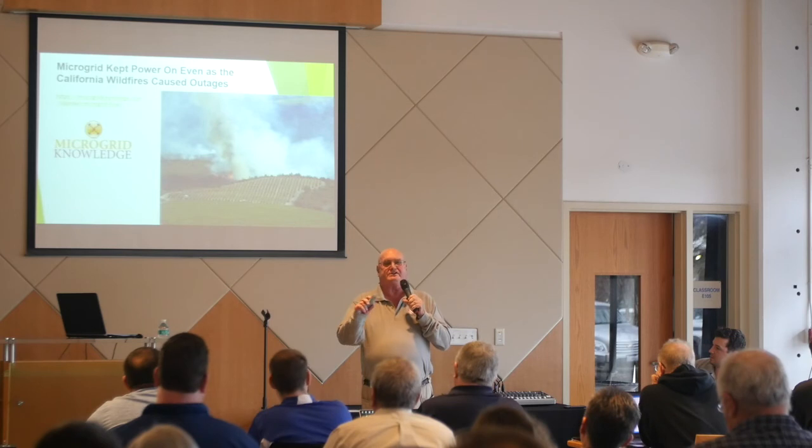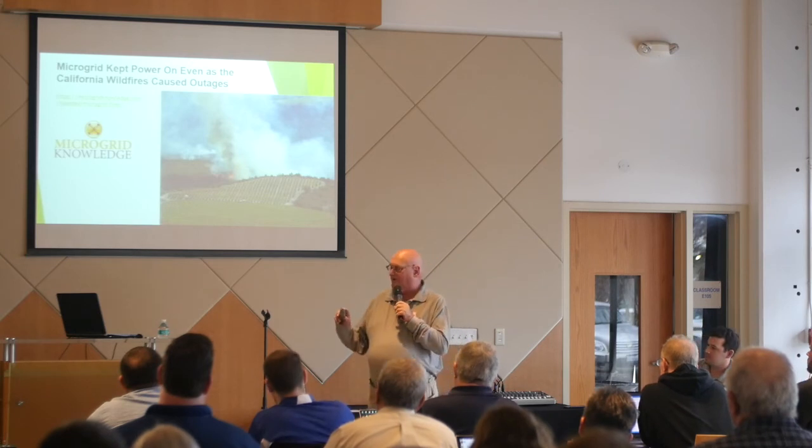For the next 10 days, we operated. Here's what's really funny, and the part that we never expected in all use cases we've written, we were all evacuated. There was no one there. Now, everybody in this room is probably going, "Well, it's a microgrid, dummy, it should sit there and work." Well, we were always figuring that somebody would be around to flip a switch, reset a breaker, do something. For 10 days, we operated totally autonomously with nobody on site.